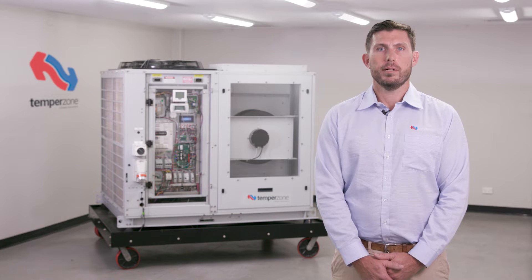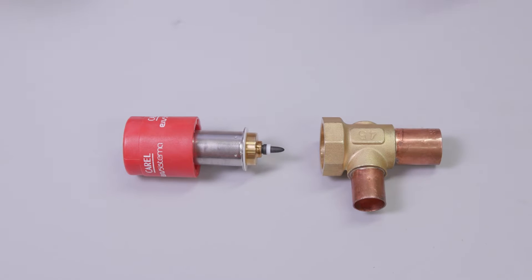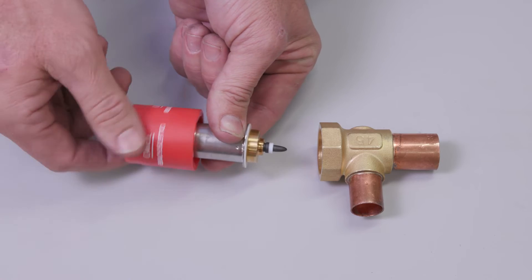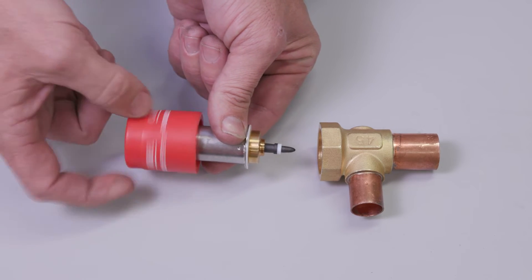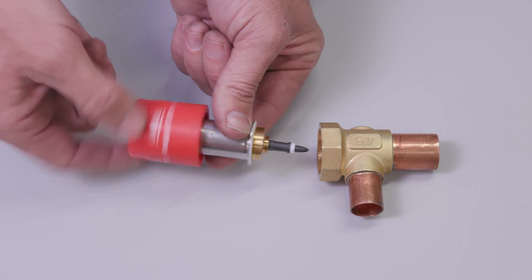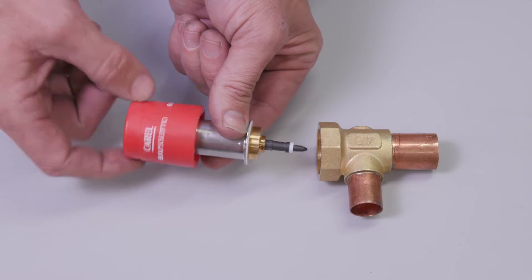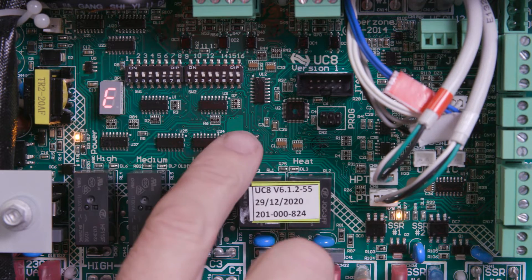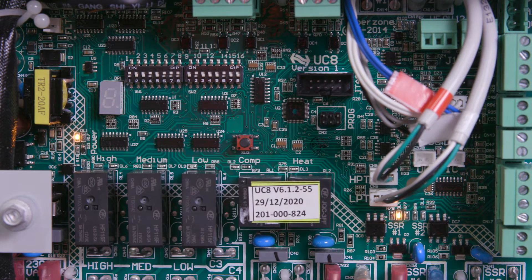An EEV operates a motor instead of an electromagnetic coil. The pulsations of the motor windings turn the valve spindle up and down a thread, allowing for modulated control of the valve, referred to as valve steps and displayed as a percentage open on the UC8 printed circuit board or Wi-Fi service utility tool.